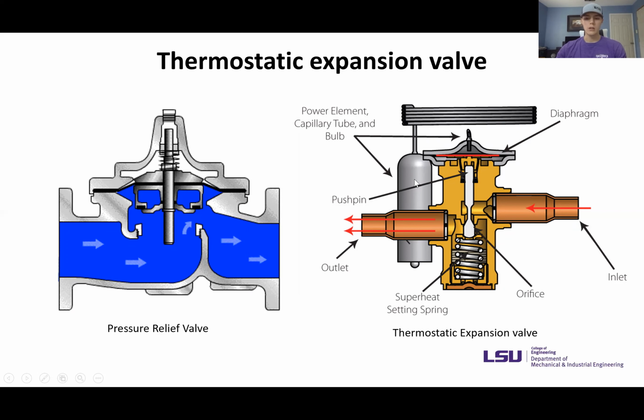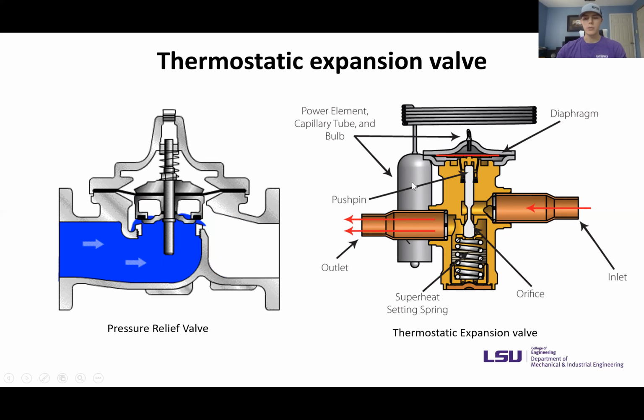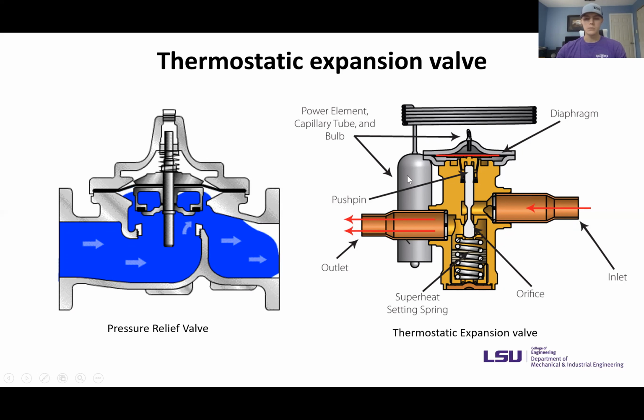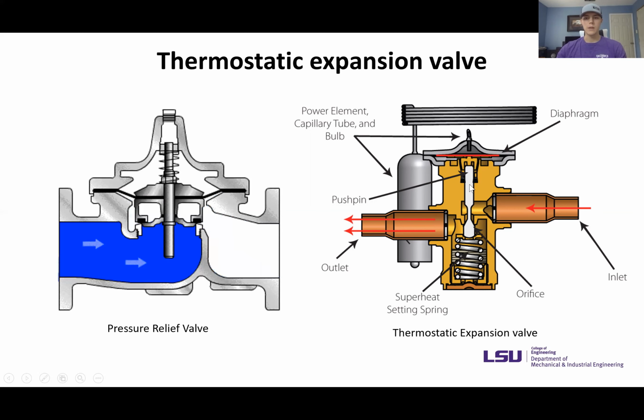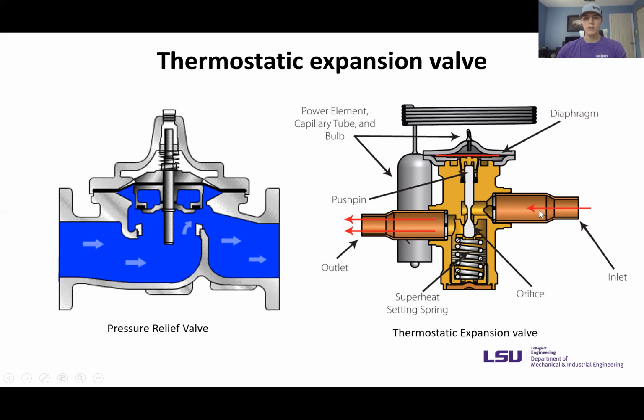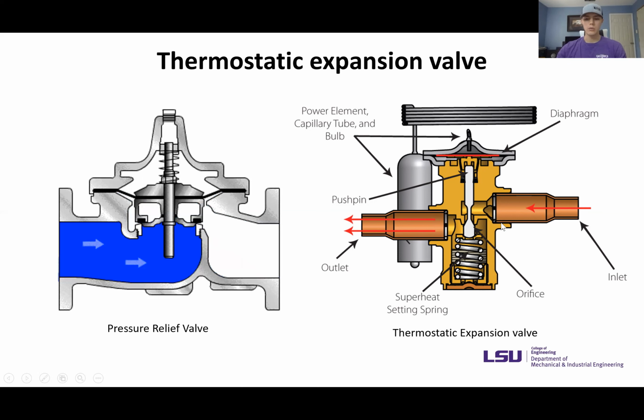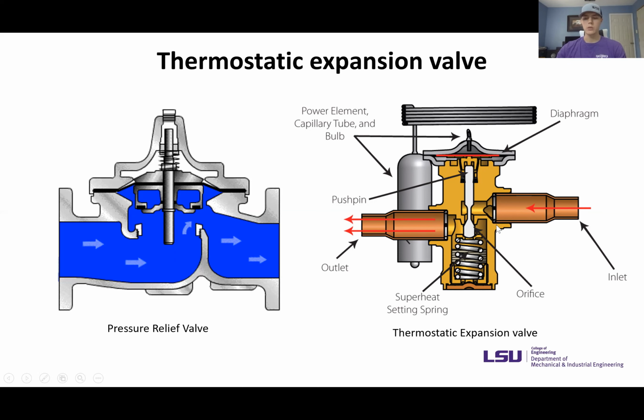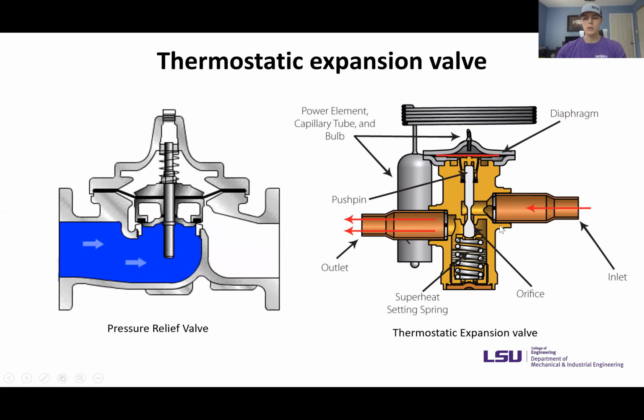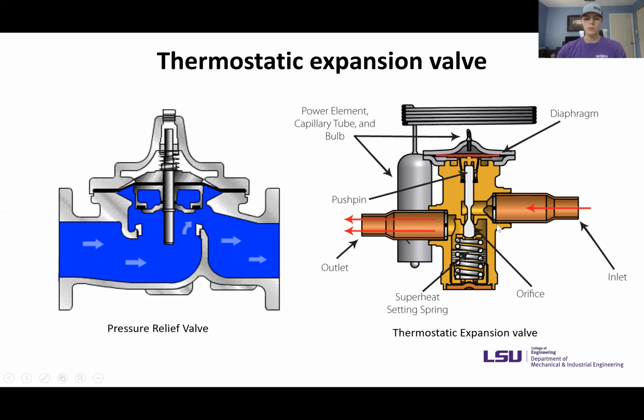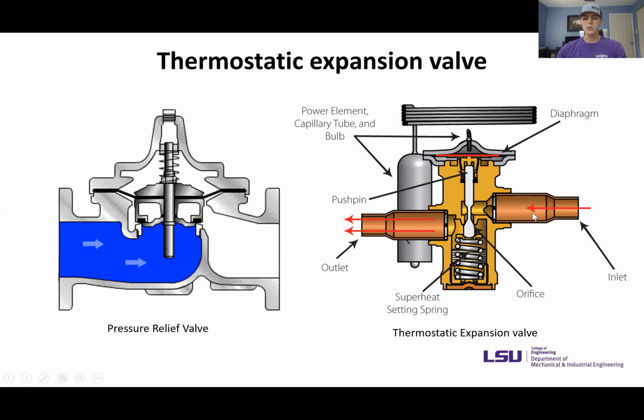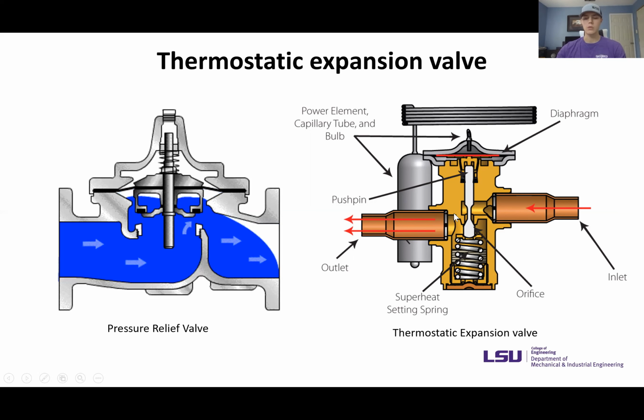So whenever the superheat from the evaporator boils the refrigerant, it creates pressure that goes through the capillary tube into the diaphragm, and the diaphragm expands, activating the pin and pushing down on the spring, allowing more refrigerant to flow through the valve. As more refrigerant flows, the superheat in the evaporator decreases. So the valve repeats consistently to ensure the correct amount of refrigerant can flow through. And the superheat can also be adjusted manually.